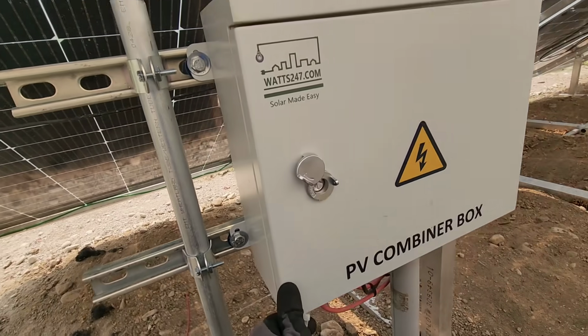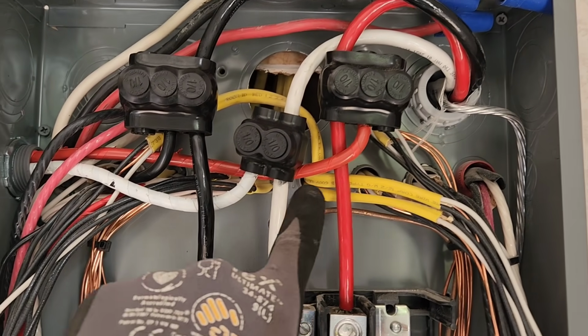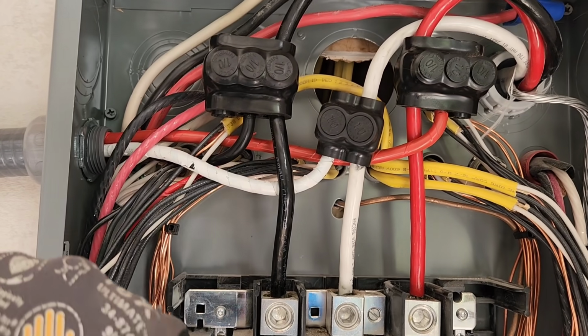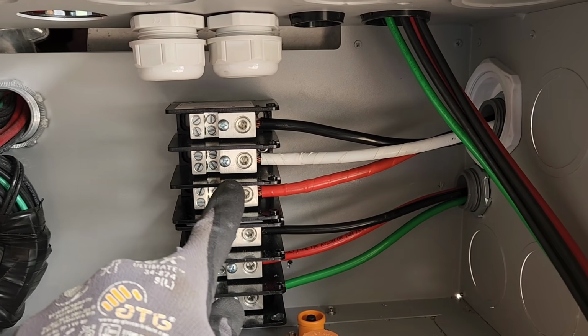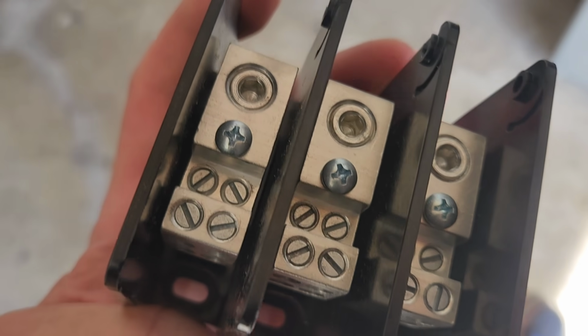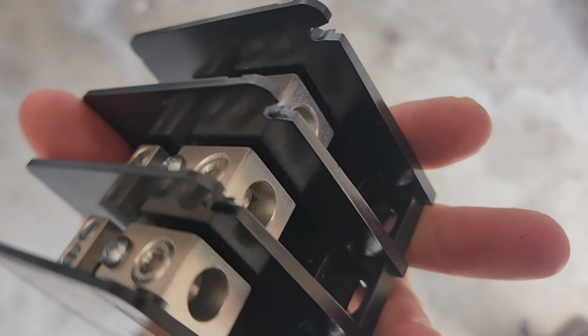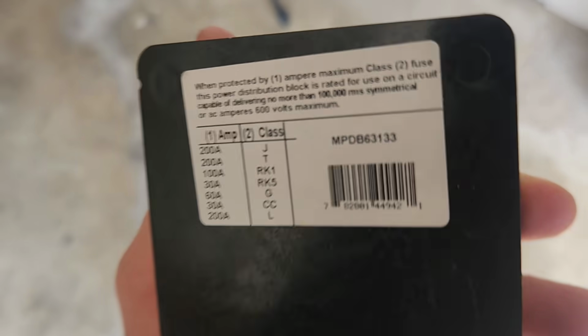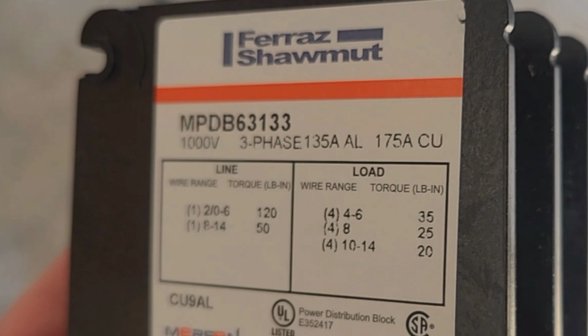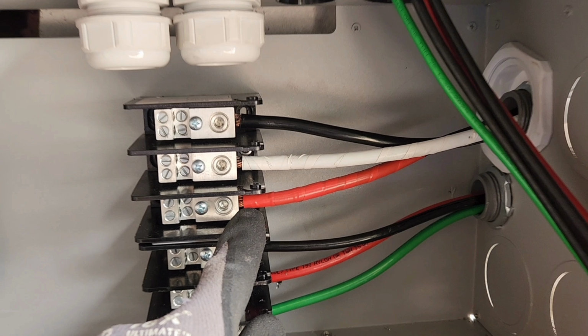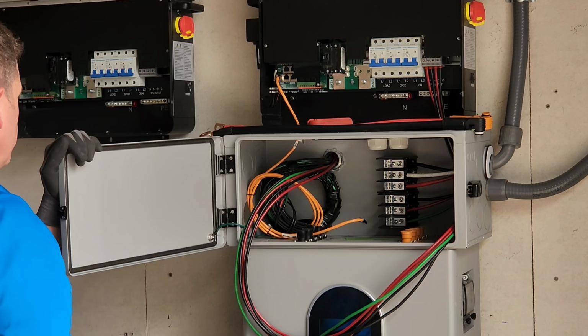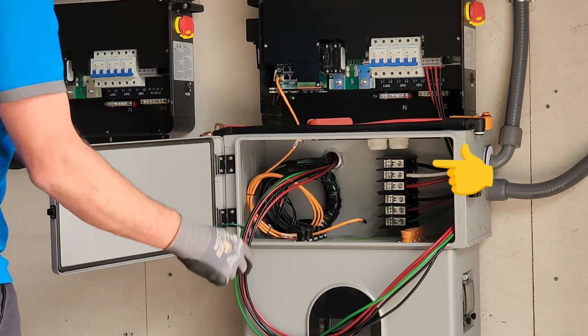Okay, we got these grid connections upgraded to a 4-gauge wire. And those come down into these power distribution blocks. Now I had to buy these distribution blocks separately online. Their job is to distribute the power to my 2 separate inverters. So the top distribution block pretty much just has my grid connection coming in, and then the bottom distribution block has the green ground, and then L1 and L2 for the power that's going out of these inverters into my backfed breaker. So my first step is I'm going to connect the grid portion to both inverters.